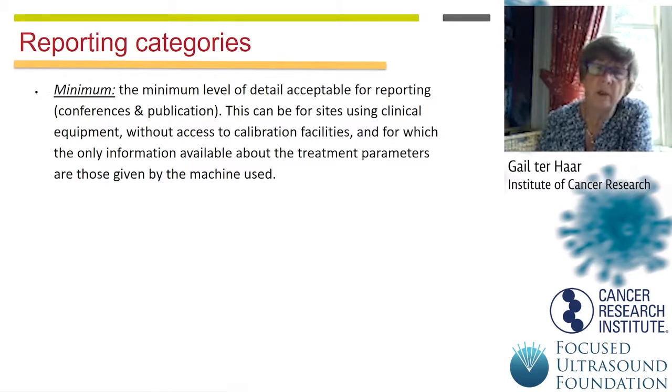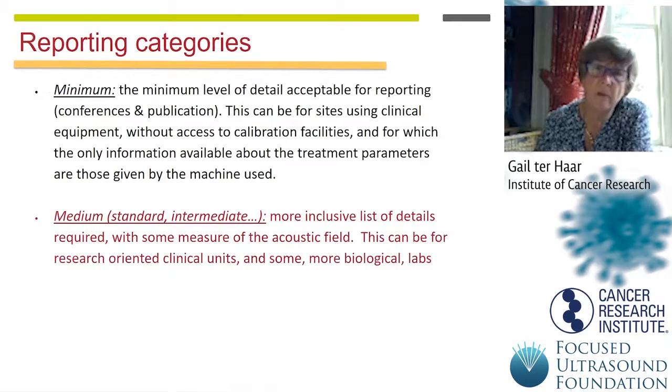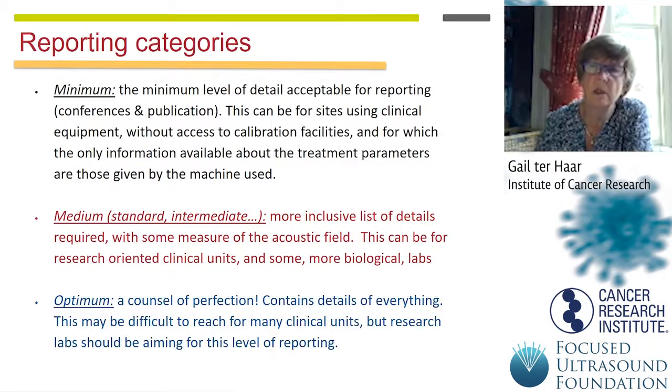At the minimum level, and we see this as being really only suitable for people in the clinic, it gives us a minimum of information about the treatments being given and the machines being used. Then we have the medium level, which is a more inclusive list of details that's being required with some measure of the acoustic fields. And we see this as being suitable or achievable and okay for research-oriented clinical units and some more biological labs who don't have access to sophisticated calibration techniques.